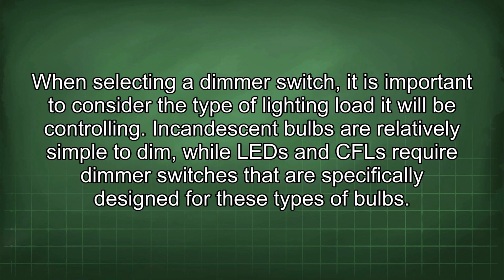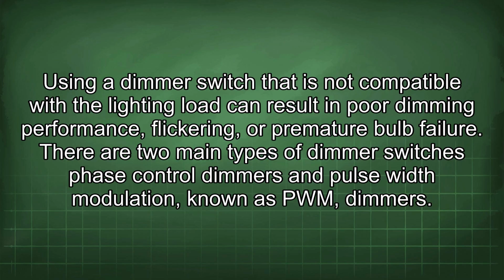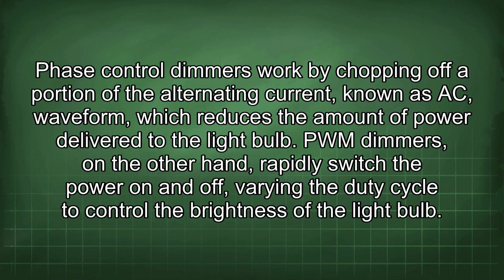When selecting a dimmer switch, it is important to consider the type of lighting load it will be controlling. Incandescent bulbs are relatively simple to dim, while LED and CFL require dimmer switches that are specifically designed for these types of bulbs. Using a dimmer switch that is not compatible with the lighting load can result in poor dimming performance, flickering, or premature bulb failure. There are two main types of dimmer switches: phase-controlled dimmers and pulse-width modulation, known as PWM dimmers. Phase-controlled dimmers work by chopping off a portion of the alternating current, known as AC, waveform, which reduces the amount of power delivered to the light bulb.